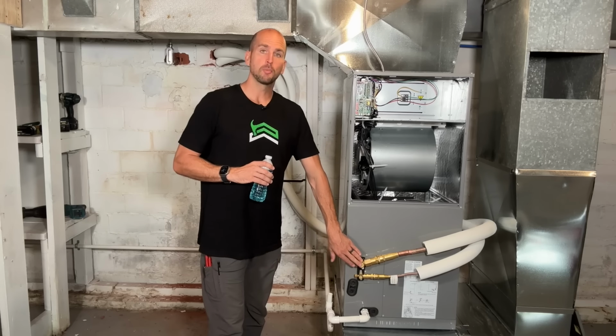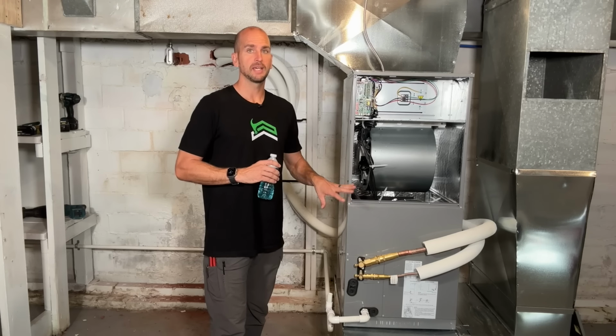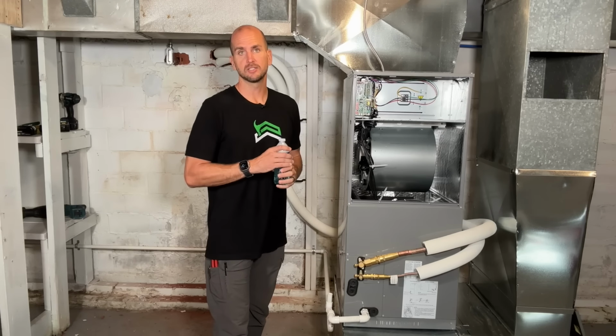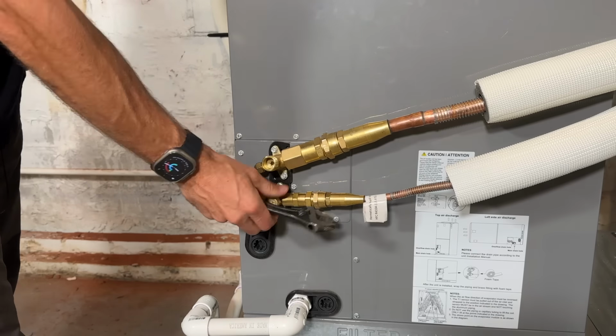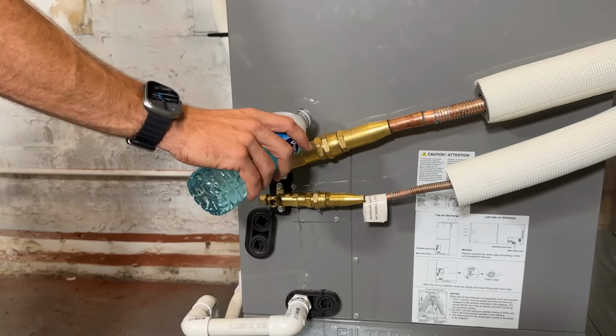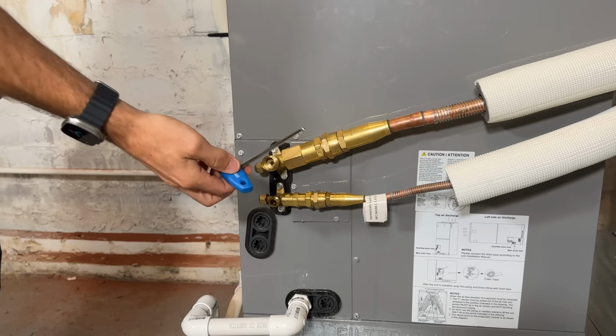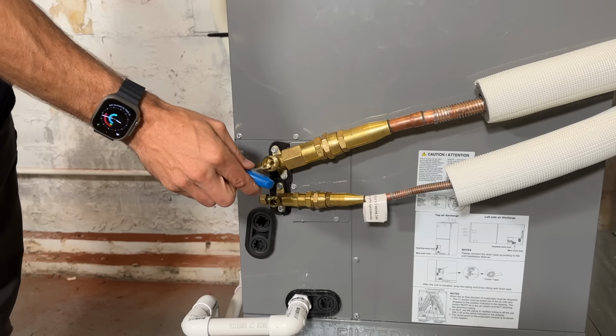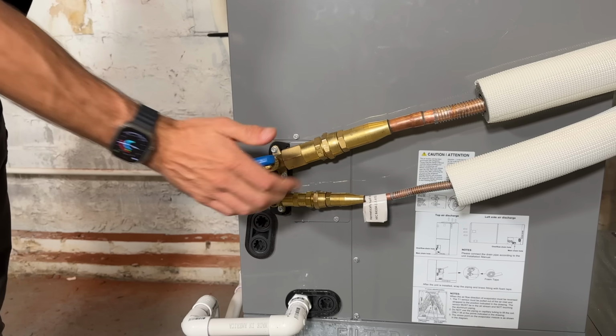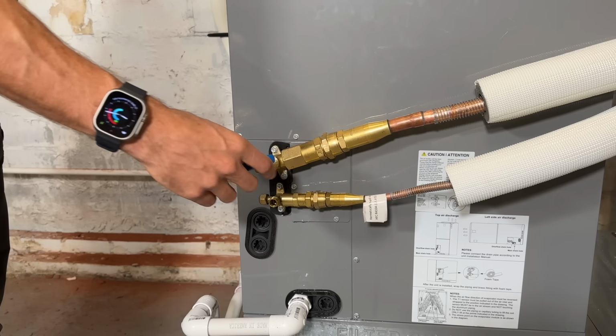Let's go ahead and open the valves here to let the refrigerant in, both at the air handler and the outside condenser. Then open these up. They do give you a 5mm Allen wrench. All you have to do is just turn it all the way to the left until it stops.